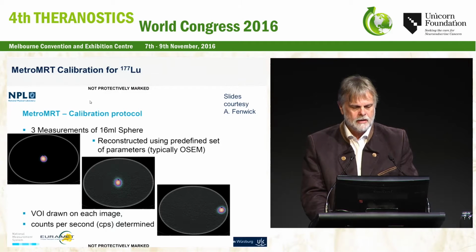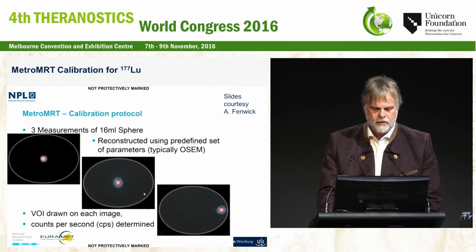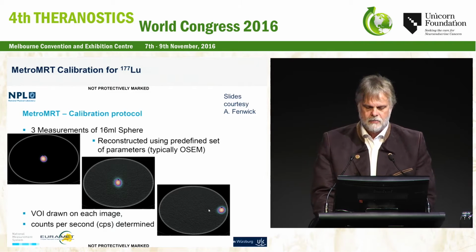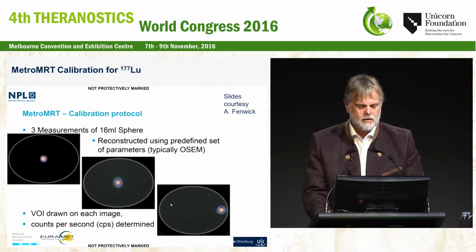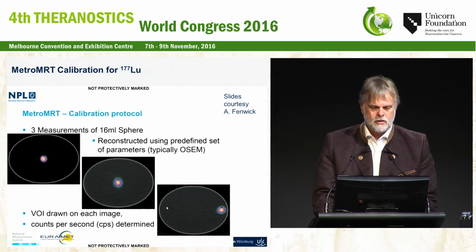They set up a calibration protocol of spheres with 3 measurements, with and without water, just to test how the attenuation correction works and also how the scatter correction works, and one off-center image, for example, to show that the quantitation is not wrong if you're off-center. So that's one way of calibrating the cameras. There are other ways of doing that, but that is a crucial step.